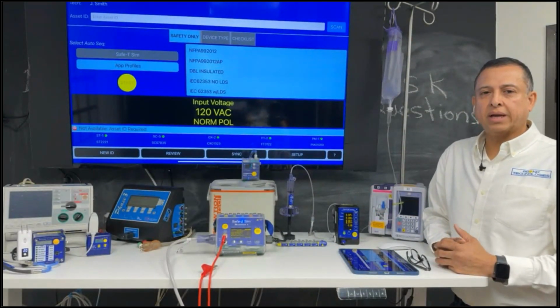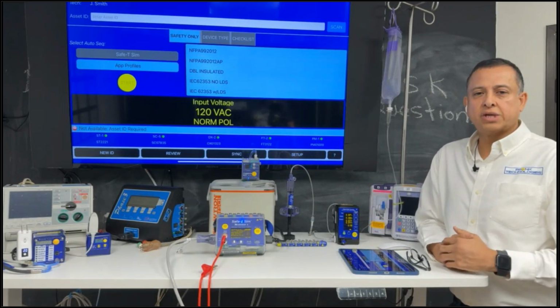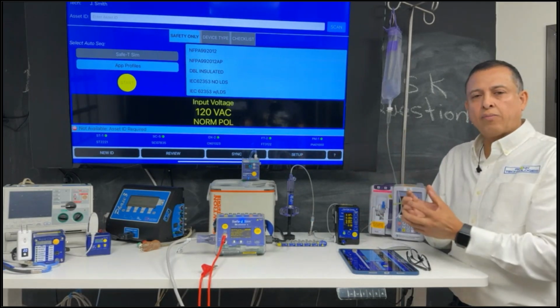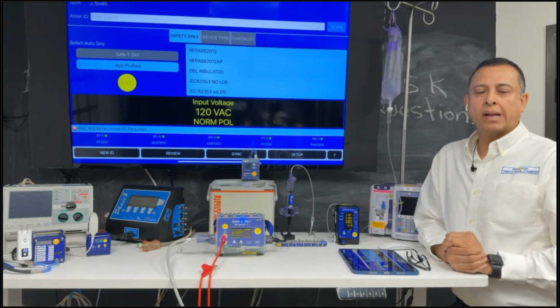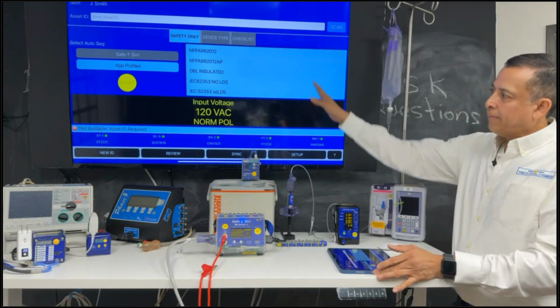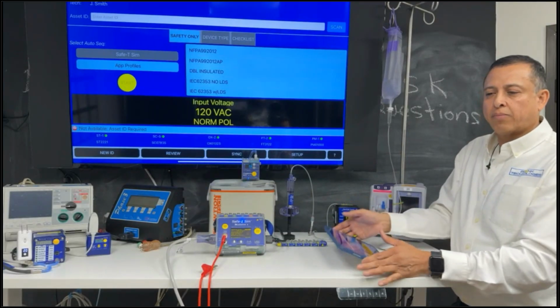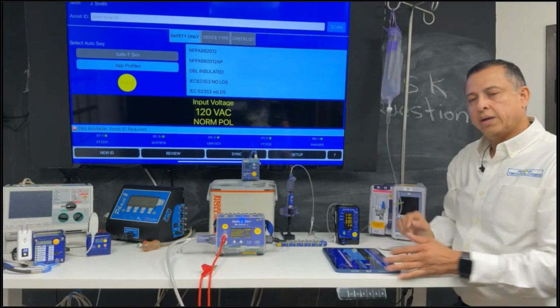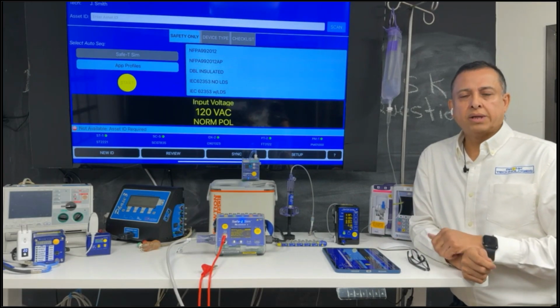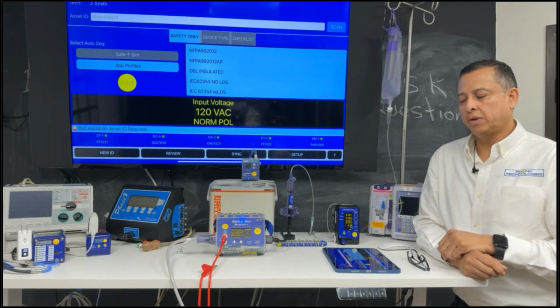The concept is to give you the ability to control these devices, have them execute the tests that you've designed and programmed, and have all this test equipment funnel all of their data back into our mobile app so that you can generate a complete electronic report. What you're seeing on the back screen is a display. We're actually running the app on an Apple iOS device, but for purposes of the demonstration, I put it up on the big screen. We also have the Android version of the Mobilize app in beta now, and we're going to be releasing the Windows version of the Mobilize app so that it fits different applications and different devices that you may be utilizing.